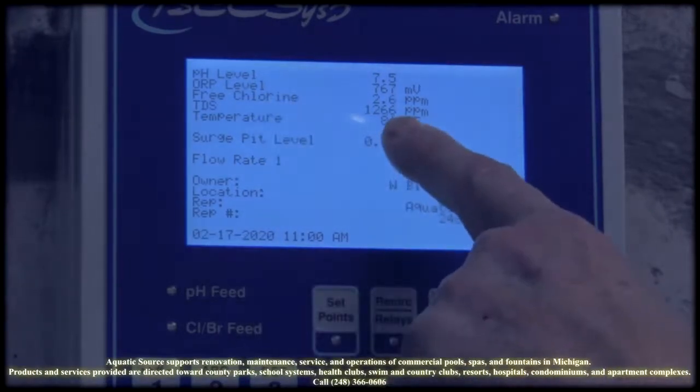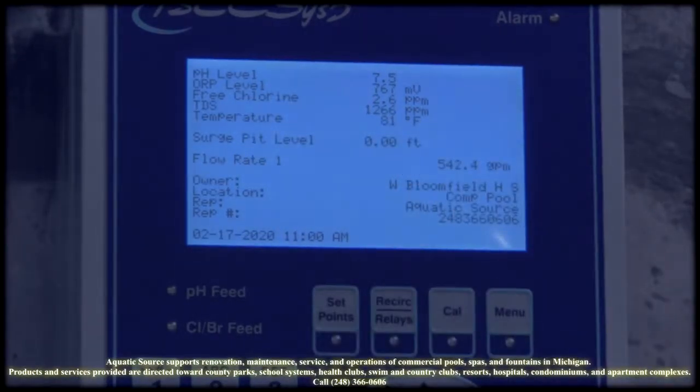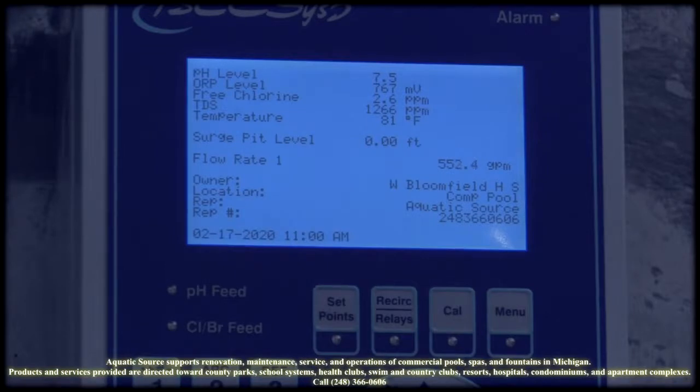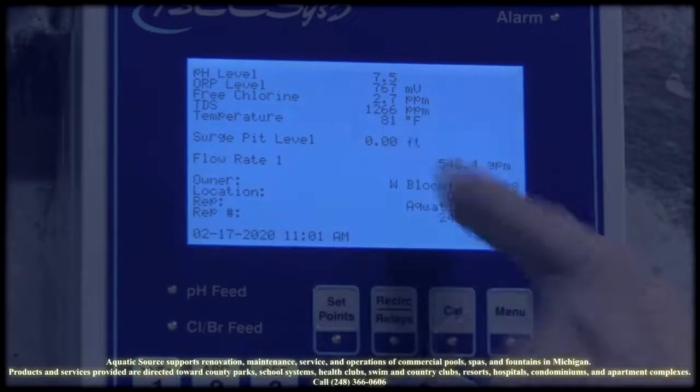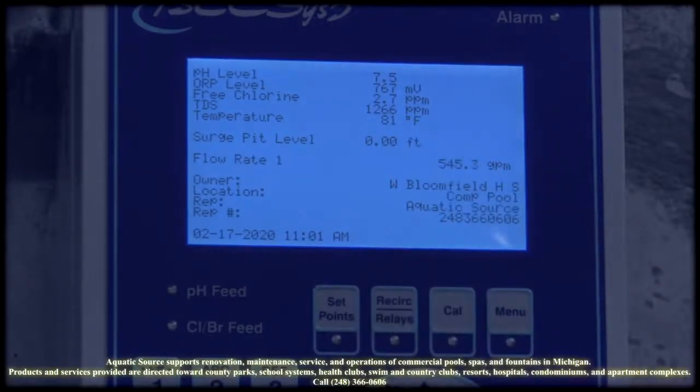We have total dissolved solids on this one is 1266. We want to keep it somewhere around that 1500. We also have a surge pit level. If the surge tank, for some reason, starts to overflow from a power or pump shutdown, it will actually send an alarm through the ethernet to the operator's phone, either a text or an email.